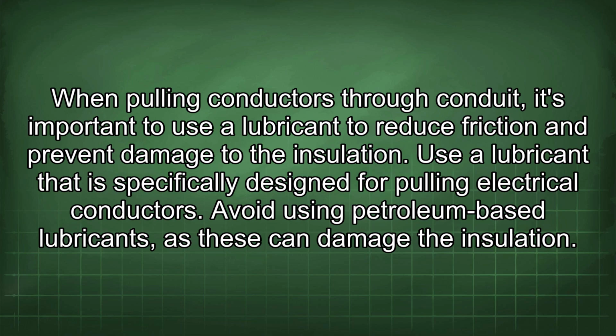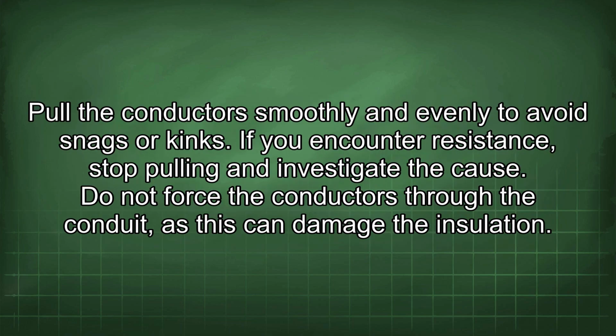When pulling conductors through conduit, it's important to use a lubricant to reduce friction and prevent damage to the insulation. Use a lubricant that is specifically designed for pulling electrical conductors. Avoid using petroleum-based lubricants, as these can damage the insulation. Pull the conductors smoothly and evenly to avoid snags or kinks. If you encounter resistance, stop pulling and investigate the cause. Do not force the conductors through the conduit, as this can damage the insulation.